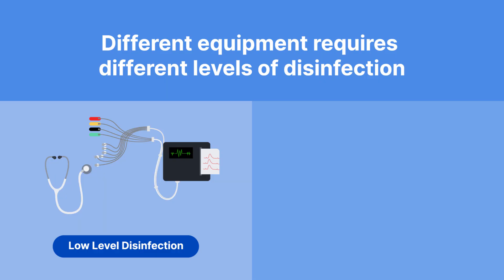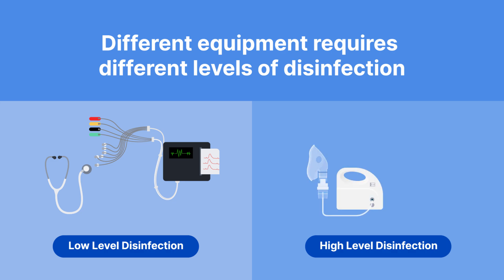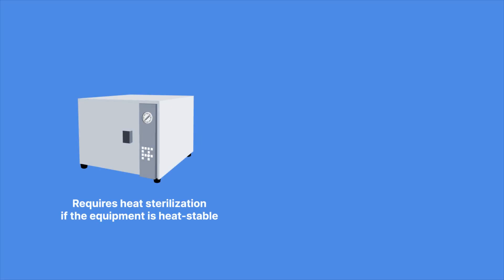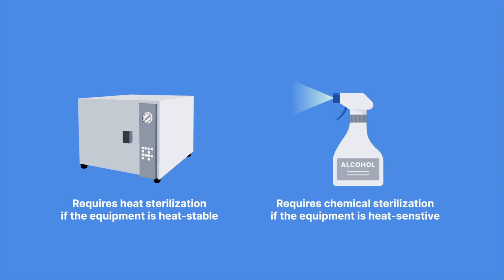Different equipment requires different levels of disinfection. Equipment that requires low-level disinfection, or just cleaning, includes blood pressure cuffs, stethoscopes, electrocardiogram leads, and environmental surfaces including the OR table. Equipment that requires high-level disinfection by heat or chemicals includes respiratory therapy and anesthetic equipment, flexible endoscopes, vaginal specula, reusable bedpans and urinals or urine bottles, and patient bowls. Equipment that requires sterilization — either by heat if heat-stable, or by chemical if heat-sensitive — includes surgical instruments, implants, prostheses and devices, urinary catheters, cardiac catheters, needles and syringes, dressings, sutures, delivery sets, dental instruments, rigid bronchoscopes, and cystoscopes.